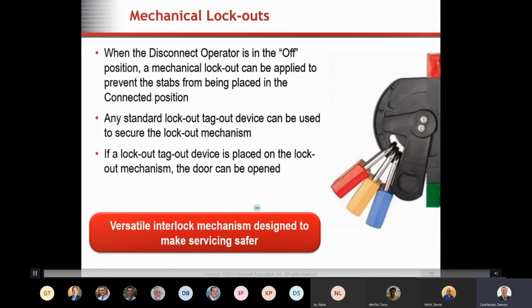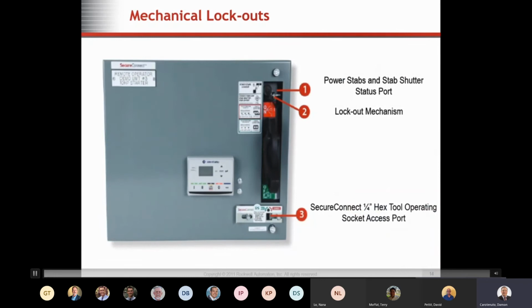So let's see what the next one is here. This is a little more detail of what the video shows. If you look at number 1, that's sort of a repeat of power stabs and stab shutter status port. But if you'll notice item number 2, you pull that pin out and put a padlock in there, and even if the disconnect's off, it will stop anybody from being able to engage those stabs. So that's another level of safety in there. And of course, they showed you the 1/4 inch hex operating tool port, but I did want to spell out the additional lockout mechanism for the stabs, so that even if it is off, no one can come by and arbitrarily connect the stabs to the bus.